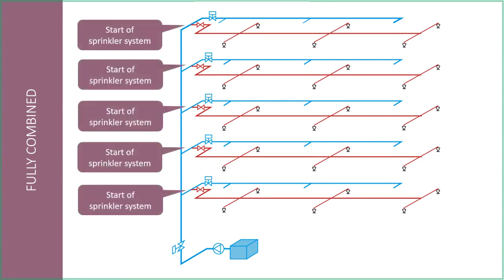What it does mean, with this kind of combined arrangement, is that effectively you've got a sprinkler system on each floor, because that's where the sprinkler system starts. The start is at each floor. It's a bit like you've got a town main system. The town main is kind of running vertically, but if you imagine it running down the street, and each floor being a separate building on the street, it's a bit like that. So the start of the sprinkler system is on each floor level.